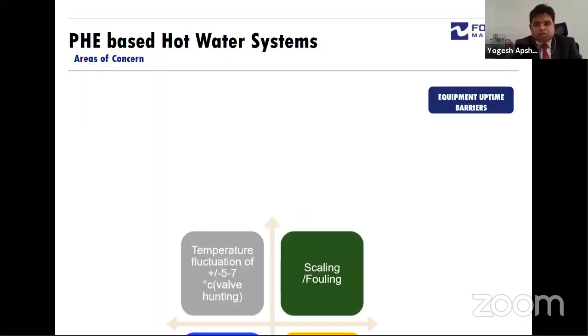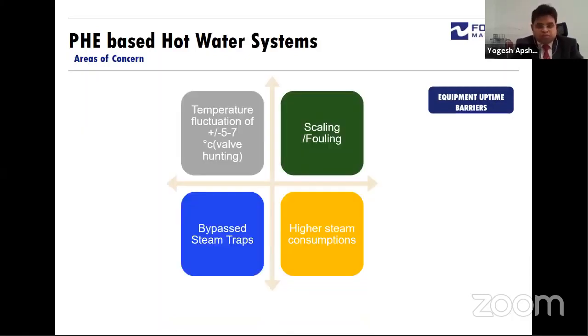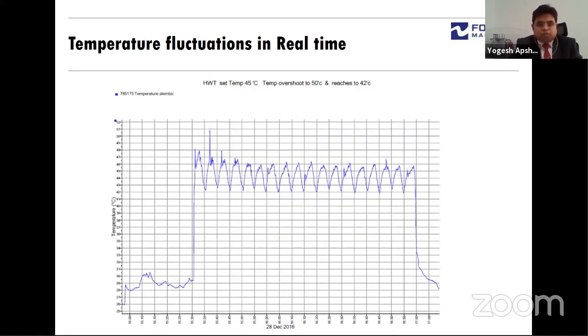Hot water generation systems are one of the major consumers of steam in formulation plants. In the PHE based hot water systems, we have seen temperature fluctuations of 5 to 7 degrees Celsius because of hunting of a control valve, then scaling and fouling of the PHE, the steam trap bypass being opened a greater number of times, and higher steam consumption because of the bypass opens. If you look at the temperature profiles, when we set a temperature of 45 degrees Celsius in the hot water system, we have seen the temperature overshooting to 50 degrees Celsius or undershooting to 42 degrees Celsius, which compromises the production.